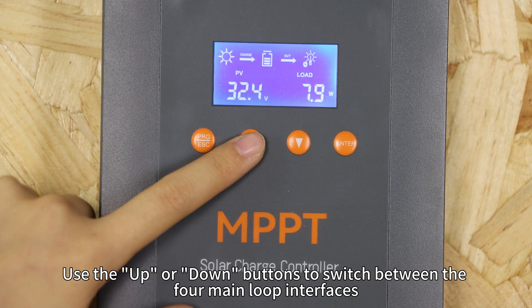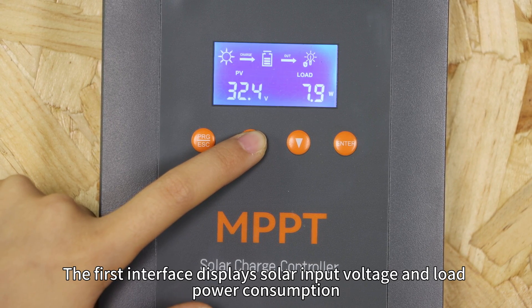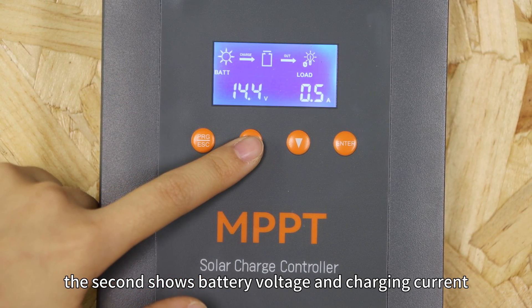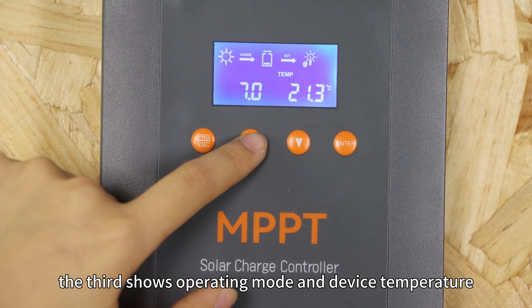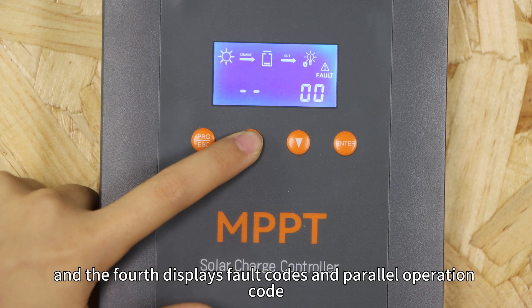Use the up or down button to switch between the four main loop interfaces. The first interface displays solar input voltage and load power consumption. The second shows the battery voltage and charging current. The third shows operating mode and device temperature. And the fourth displays the fault code and parallel operation codes.